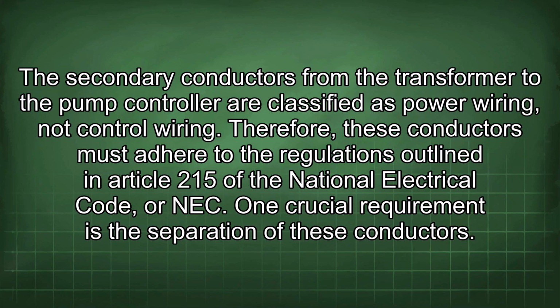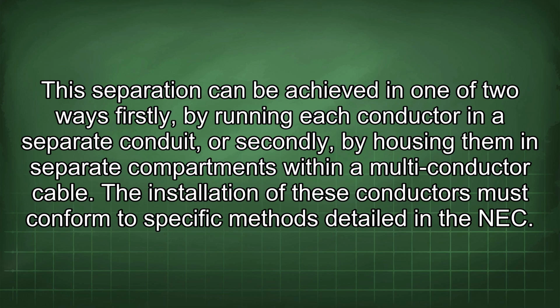The secondary conductors from the transformer to the pump controller are classified as power wiring, not control wiring. Therefore, these conductors must adhere to the regulations outlined in Article 215 of the National Electrical Code, or NEC. One crucial requirement is the separation of these conductors. This separation can be achieved in one of two ways.